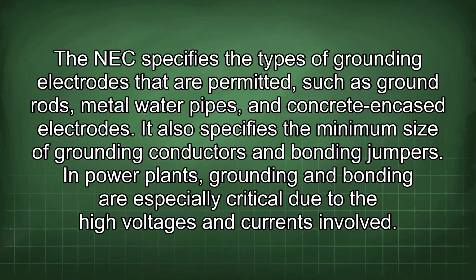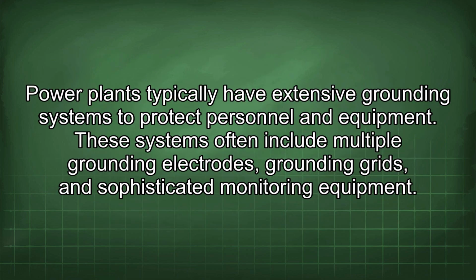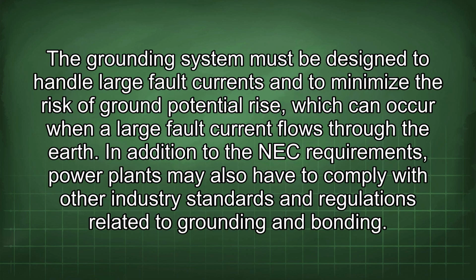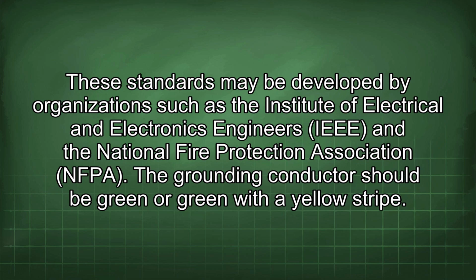In power plants, grounding and bonding are especially critical due to the high voltages and currents involved. Power plants typically have extensive grounding systems to protect personnel and equipment. These systems often include multiple grounding electrodes, grounding grids, and sophisticated monitoring equipment. The grounding system must be designed to handle large fault currents and to minimize the risk of ground potential rise, which can occur when a large fault current flows through the earth. In addition to the NEC requirements, power plants may also have to comply with other industry standards and regulations related to grounding and bonding. These standards may be developed by organizations such as the Institute of Electrical and Electronics Engineers (IEEE) and the National Fire Protection Association (NFPA).